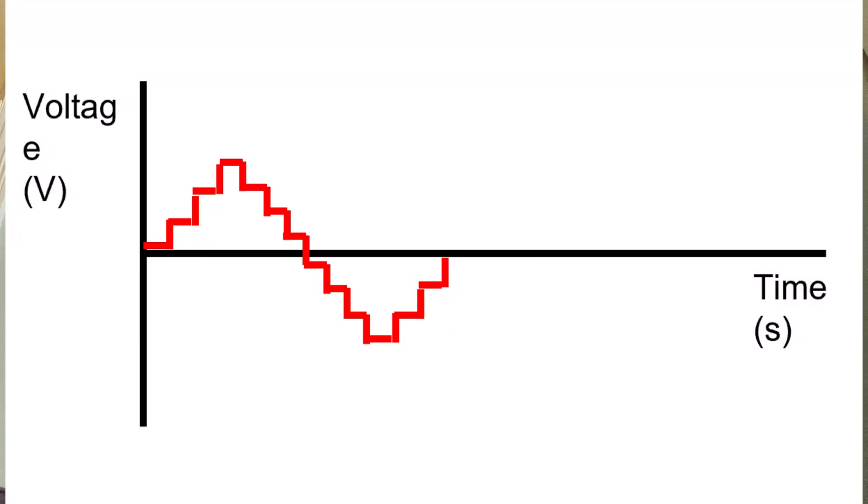So there have been improvements to how inverters work and they work by smoothing out this alternating current into a sinusoidal wave. The way that they do that is by something called pulse modulation. Effectively when the black switches in that diagram close what they do is actually open them very quickly and close them very quickly, and I mean incredibly quickly. What this does is that the voltage is on for a very short period of time and then off for a short period of time. Then they close it for a little bit longer and open it for a little bit less time. And what this does over time is it averages the voltage out as the voltage actually increases. As you can see from this graph it actually produces this step-like function.